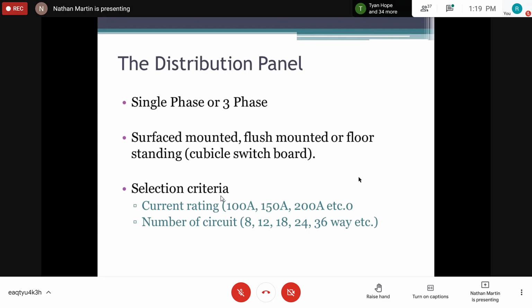A single-phase panel will have two bus bars for carrying current, while a three-phase panel will have three bus bars for carrying current, right? It will also have an earth terminal, and it will have a neutral terminal. Now, most panels in current time, meaning present, right, most panels will come with a connection between your earth bar and your neutral bar, right? It's still good to link the two with cables, right? So we don't rely on that, but we still link our supplies with cables.